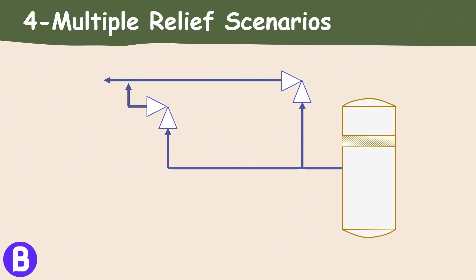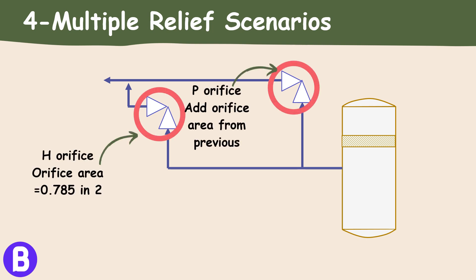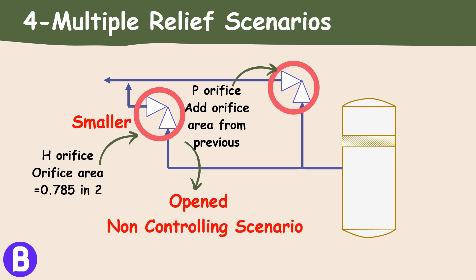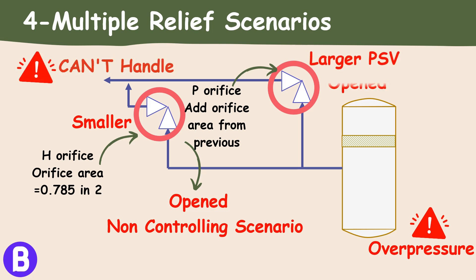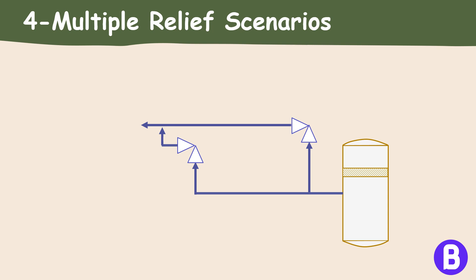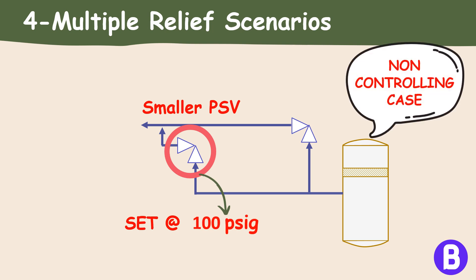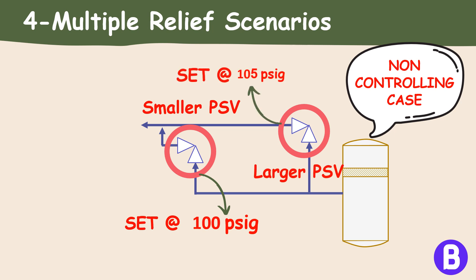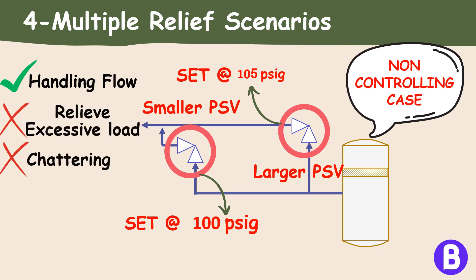One recommended solution is to install multiple PSVs with staggered set points. By employing two PSVs of different sizes, the smaller one opens first at a lower pressure, gradually relieving the system — this shall mainly be utilized in the non-controlling scenario. If overpressure still occurs and the small PSV cannot handle it, the larger PSV shall open. For example, if the set pressure is 100 PSIG, a smaller PSV opens at 100 PSIG for inlet valve failure, and if pressure continues to rise, the larger PSV opens at 105 PSIG, handling the higher flow requirements without causing excessive load and PSV chattering.